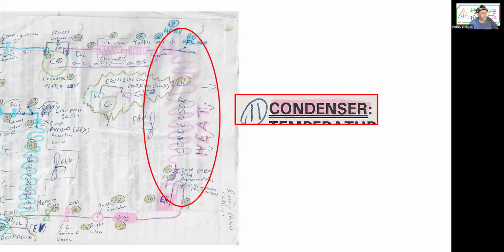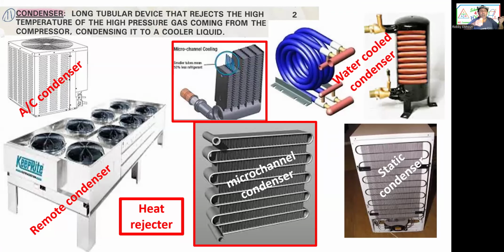But let's move on now to the condenser, to the heat rejector, huh? Heat rejector, we know what the condensers are by now. But there's a lot more going on. I will do a class just for the condensers. Condenser, the heat rejector. It's a long tube that rejects the heat. Okay, and in the condenser, first we have Freon comes in superheated from the compressor, superheated from the compression. Then it desuperheats in the discharge line and the beginning of the condenser, then it condenses, then subcooled.